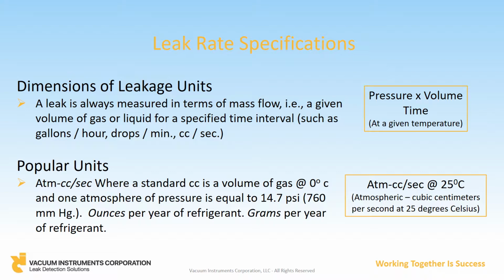Let's first understand the nomenclature behind the leak rate specification. Leak rates must always be expressed in terms of volume of gas or liquid specified over a unit of time and at a given pressure and temperature. There are many examples of this, including ounces or grams per year of refrigerant, cubic centimeters per minute, or SCCM, or perhaps the most common unit in the industry, atmospheric cc's per second.